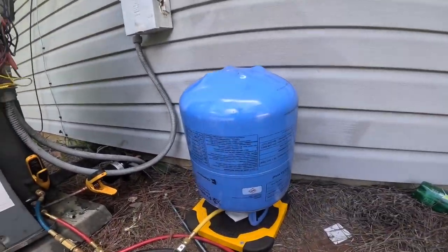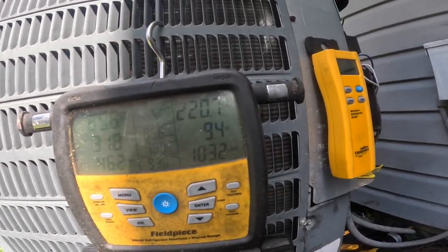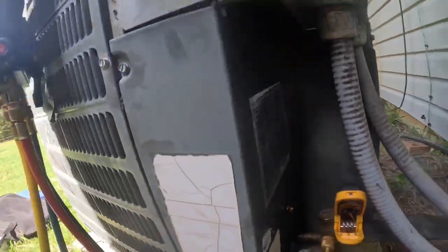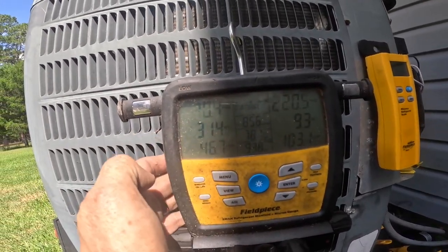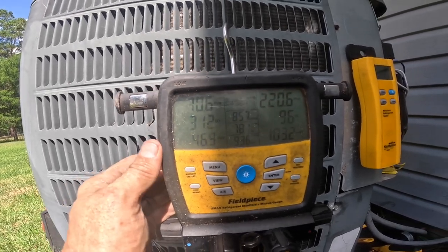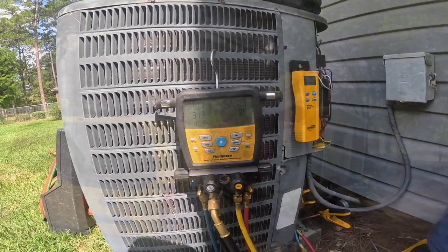This is MO99 or R438A. I had no nameplate — nothing I could read right there. So I'm just charging it up by subcooling and superheat, mostly judging by the superheat right here. It's over 80 degrees in there, and they're glad to have some air conditioning.